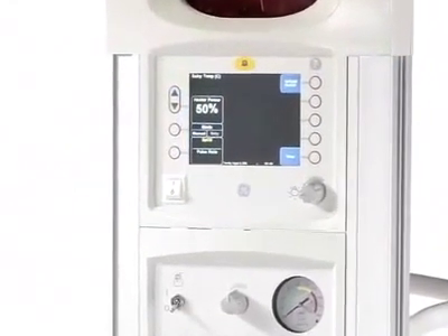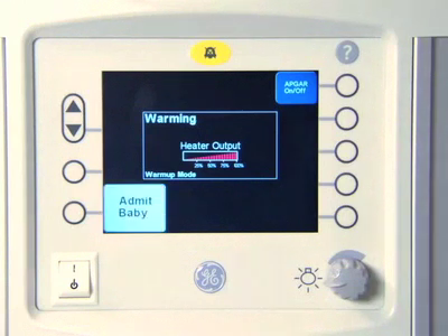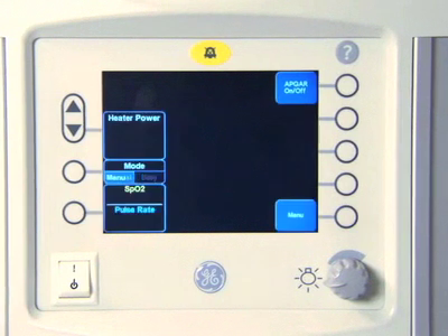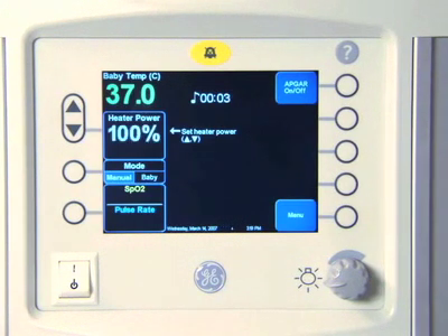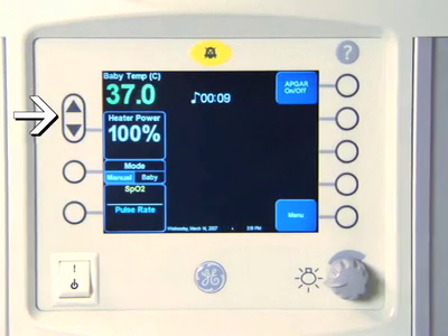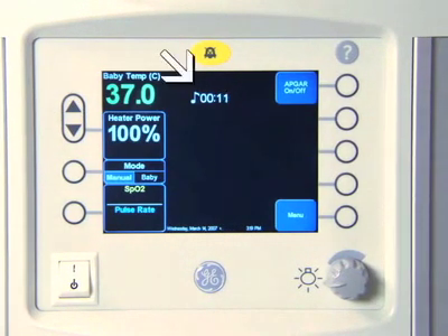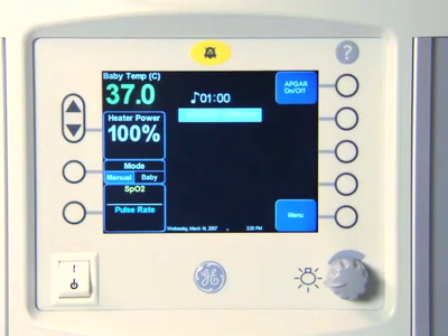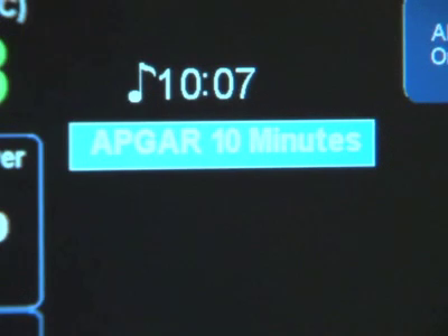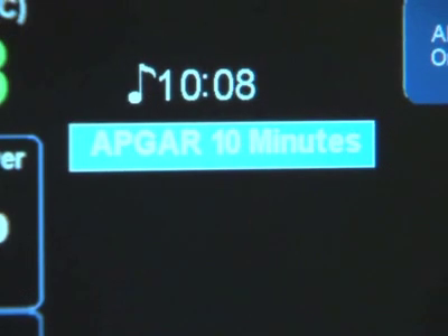The APGAR timer can be activated during all 3 operational modes. In warm-up mode, activating the APGAR timer takes the bed out of warm-up mode into normal operation in manual mode. Confirm the heater power setting by pressing the up or down arrows. When activated, elapsed time is shown on the screen. A tone sounds to alert you to the APGAR score in 1 minute, 5 minutes, 10 minutes, and every 5 minutes after that. A visual flag on the screen also alerts you to the 1, 5, and 10-minute APGAR time.